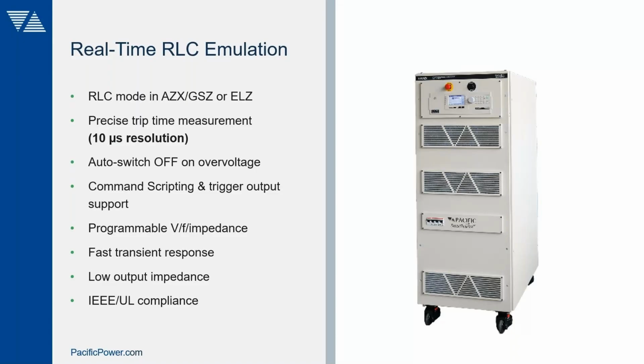They are all regenerative, so they're very capable of managing the power flow in both directions. The built-in measurement scope capabilities are high resolution, down to 10 microseconds, so they can accurately capture the time between the grid disconnect and the DER turning off. So you get a good capture of the voltage and current, as well as the time that it took to accomplish that. And then, scripting commands are available on these units as well. It also has an external trigger if you want to use an external scope or other measurement equipment.